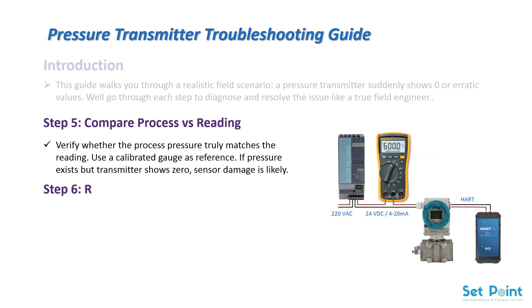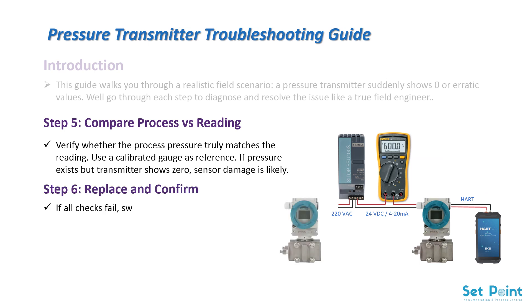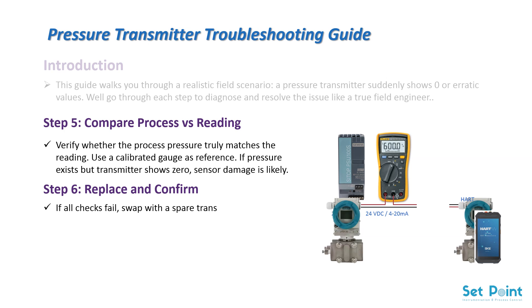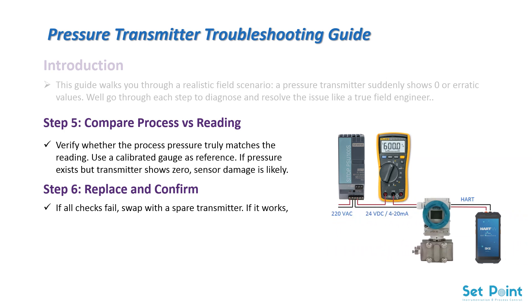Step 6: Replace and confirm. If all checks fail, swap with a spare transmitter. If it works, the original is defective. Send it for calibration or replacement.